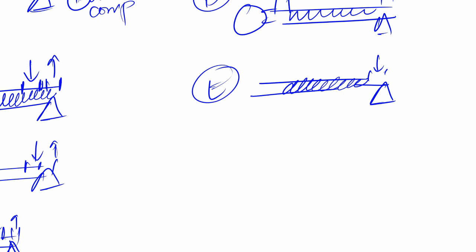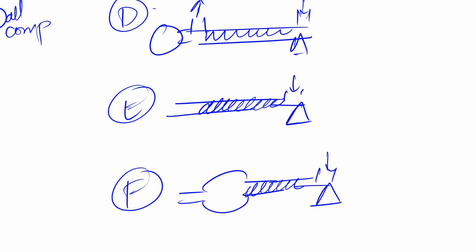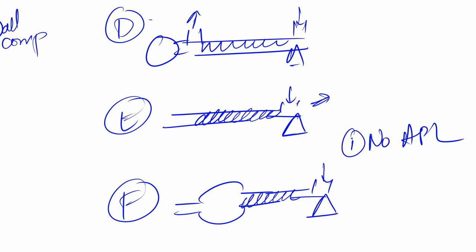Circuit D has a reservoir bag, an outlet, a corrugated tube, an inlet, and a face mask. Circuit E is open and has a corrugated tube, a fresh gas flow inlet, and a face mask. Circuit F has a reservoir bag, a corrugated tube, an inlet, and a mask. In E and F, there is no APL valve. Also, E has no bag. In D, E, and F the fresh gas flow is nearer to the patient, while in A, B, and C the APL is nearer.